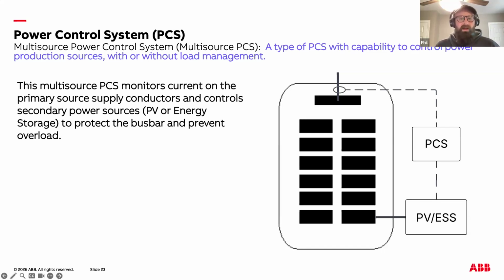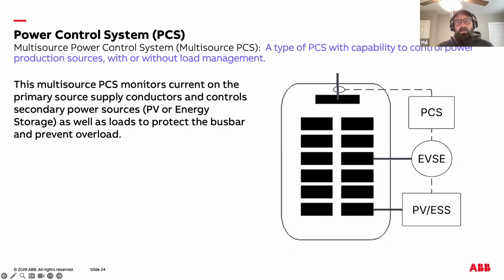At the same time, it actively controls the output of the PV ESS, adjusting or limiting its contribution whenever necessary. By doing so, the PCS ensures that the combined current from the utility source and the on-site generation never exceeds the rating of the busbar or upstream equipment. This setup illustrates how a multi-source PCS enables safe integration of distributed energy resources without requiring costly service upgrades or oversized equipment. It also highlights the real-time coordination between monitoring and control that defines PCS functionality under the 2026 code.